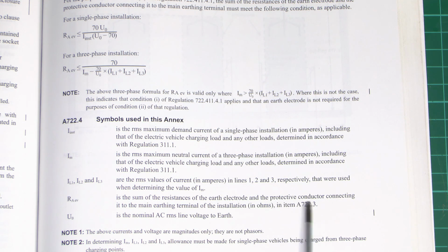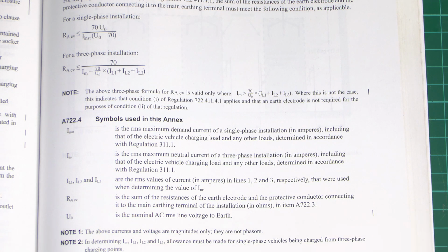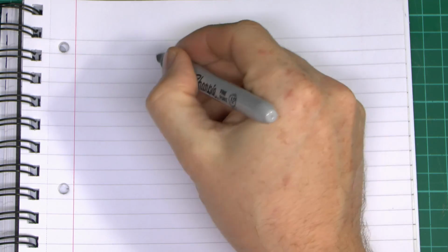Now, the protective conductor is going to be of tiny resistance anyhow, because generally it's going to be a fairly substantial piece of copper. So it's primarily going to be the resistance of the earth electrode, and that's essentially the absolute maximum that it can be. And in ideal circumstances, of course, it would be less. So let's just write that out and put some sample values in and see what kind of fail we can actually get.